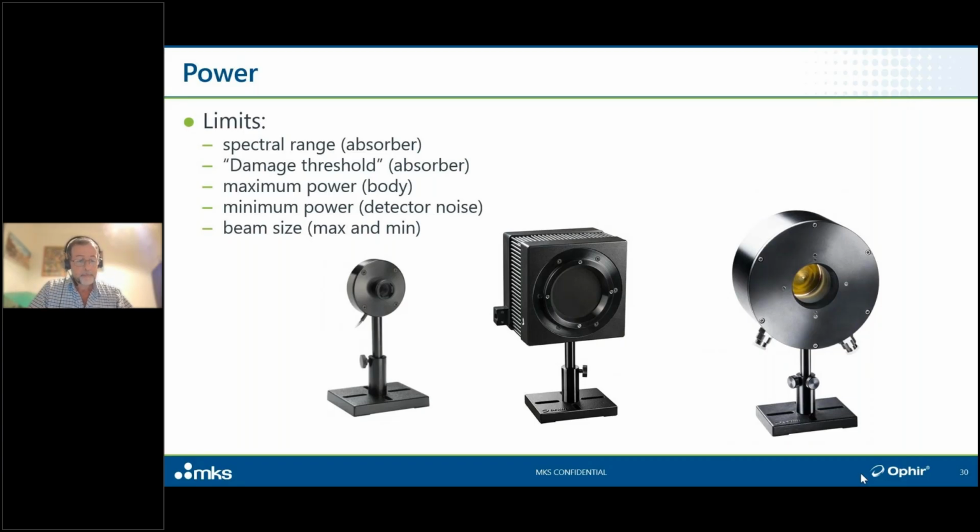Maximum beam size obviously is limited by the aperture of the sensor. Keep in mind, though, that it's not always quite as simple as that. For a Gaussian beam, for example, there's quite a bit of beam outside what appears to our eyes as the beam's outer limits.